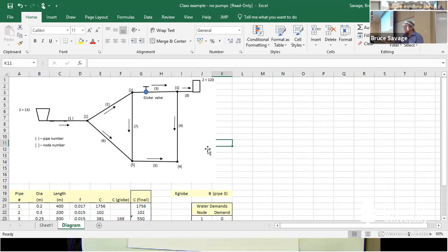So they brought in this guy, you know, who's an expert. Started looking at the system. Turns out that they had a check valve that they had put in, so water wouldn't go back into the tank when it wasn't supposed to. The fill line and the drain line for the system was the same thing, and they put the valve in backwards. So it would fill up, but it would never drain. Water would never go back into the system. So it just sat there for, you know, weeks, and it would kind of go bad.